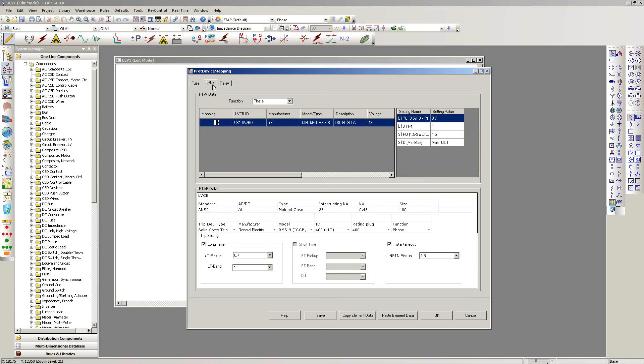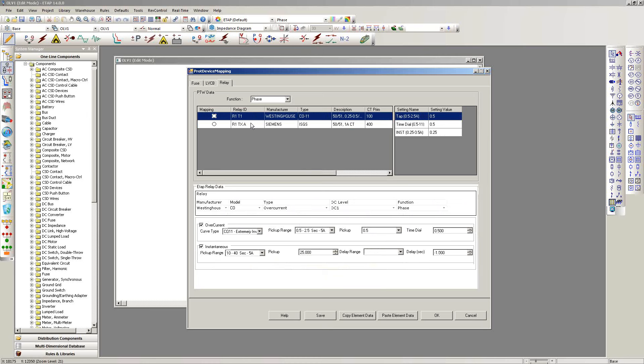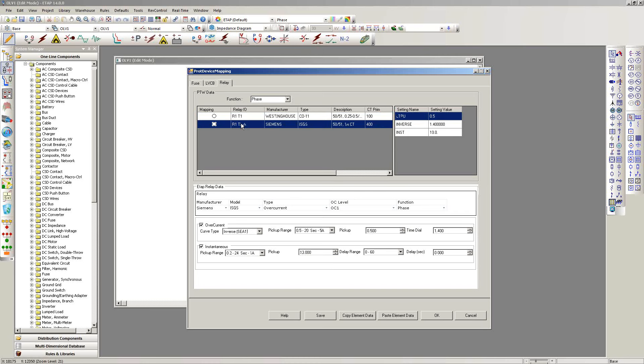On the bottom half, the equivalent data has been automatically mapped. All three fuses had an equivalent found and mapped automatically. Moving to the next tab, 'LVCB,' this is where all low-voltage circuit breakers — power circuit breakers, thermal magnetic breakers, and insulated molded case breakers — are listed, with equivalents automatically selected on the bottom half. The next tab covers overcurrent relays with functions 49, 50, and 51, showing original settings on top and mapped devices on the bottom.